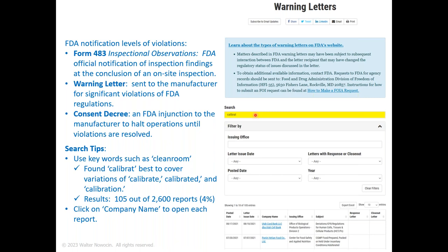When I did this more recent research, I was able to get 105 reports out of 2,600 reports that were in the inventory. So about 4% of the warning letters had a calibration finding within it. That's pretty low. If you would ask me to make an educated estimate before I ran this, on what would be the percentage of calibration issues to reports, I would have put it above 10, perhaps above 15%. So 4%, that's pretty good.